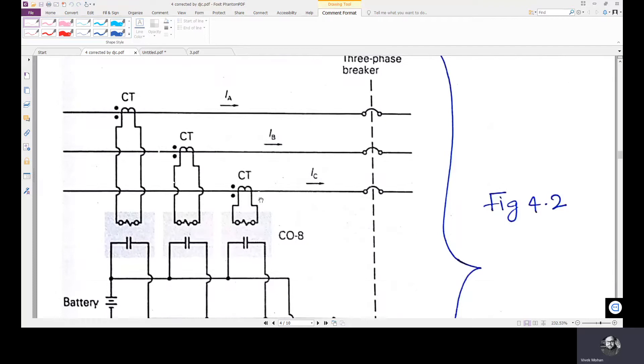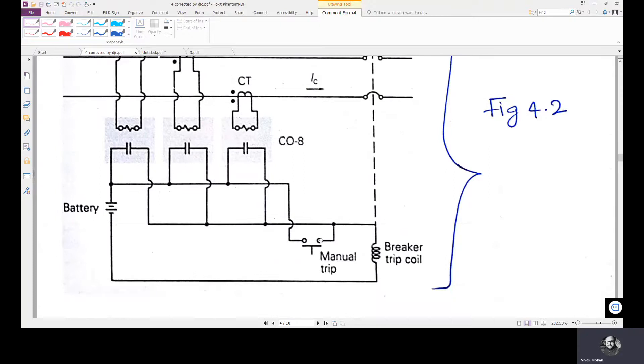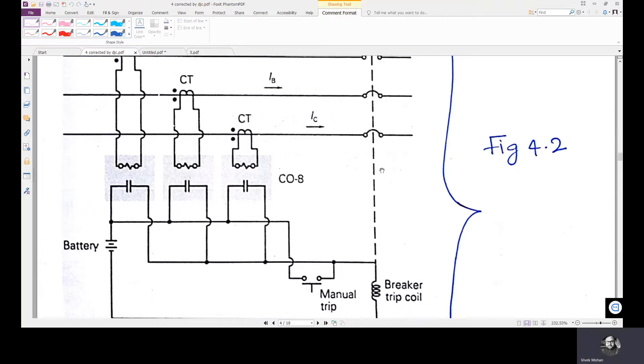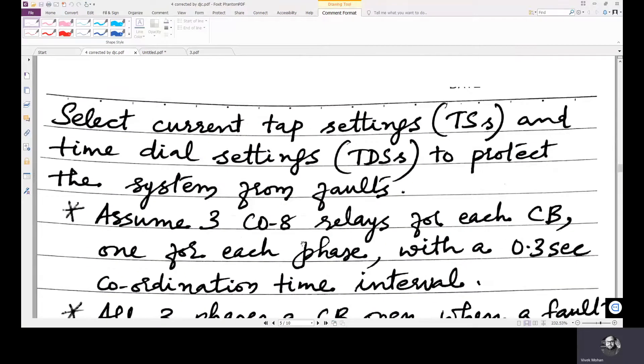The CT primary is connected to the power system where the actual lines are three-phase. IA, IB, and IC are the currents through phases A, B, and C. The CT secondaries are connected to the relay inputs, and through the relay it is connected to the breaker trip circuit. We are asked to select the current tap settings (TS) and time dial settings (TDS) to protect the system from faults.